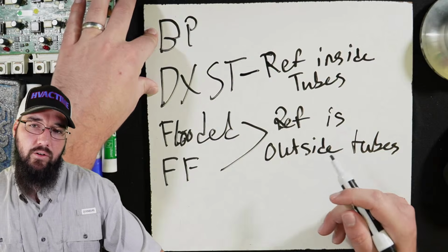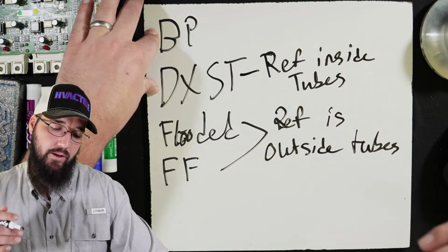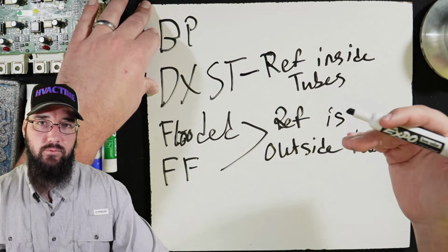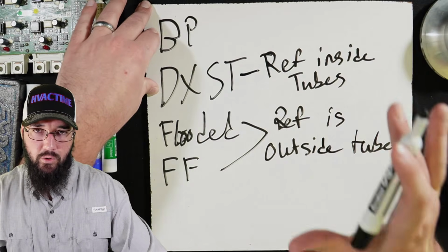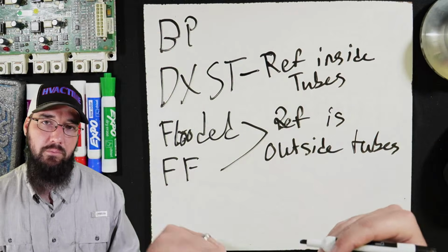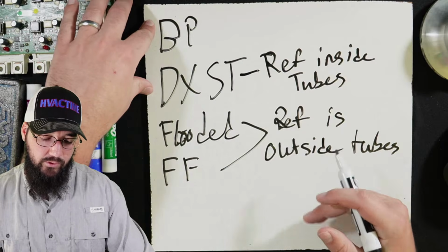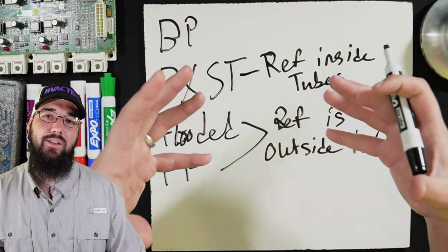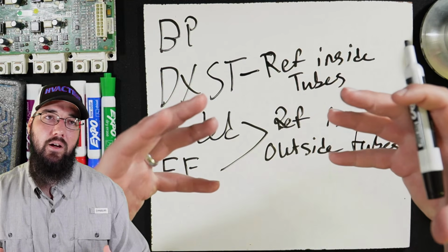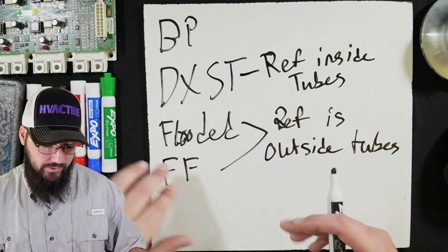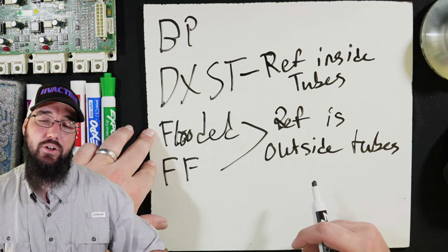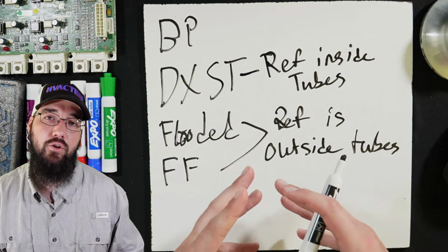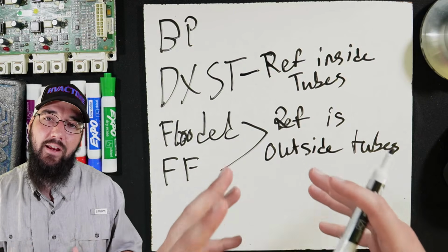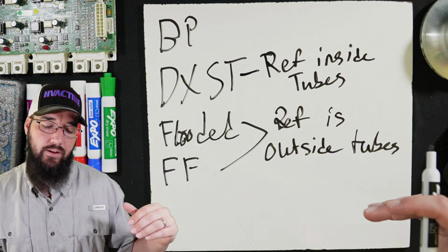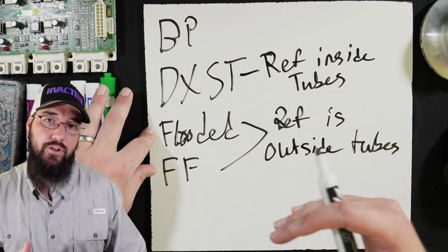So these two here both go through a pump down cycle. Okay, or typically most machines that use these will do a pump down. What that means is that the refrigerant is not being stacked in the evaporator, but that is not true for these. These actually hold the majority of the charge in the evaporator, and at shutdown, they stack a lot of that charge into the evaporator.